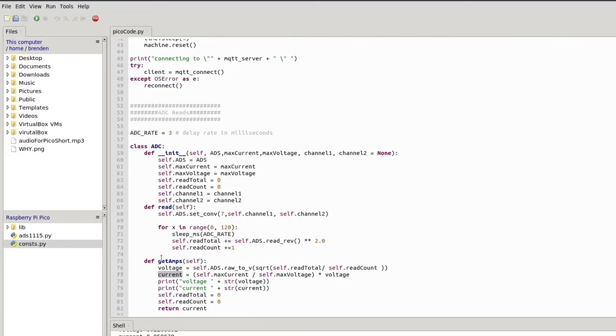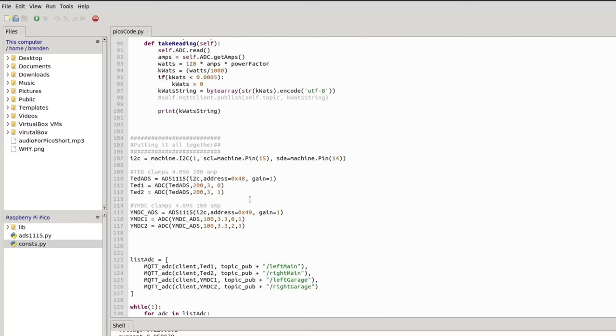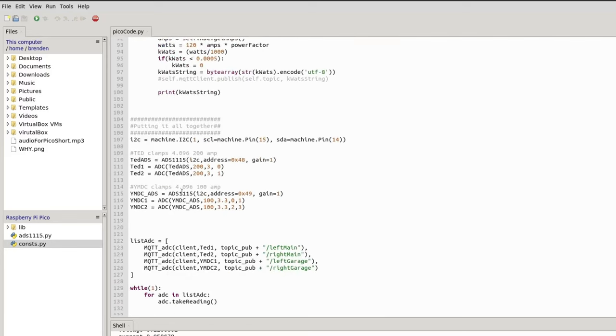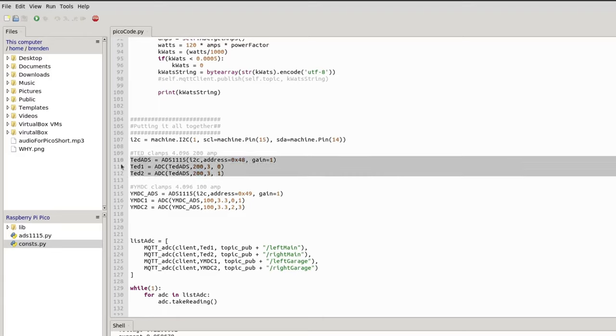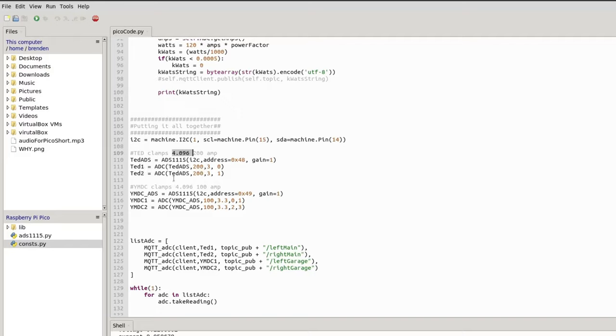These TED clamps have a gain of 1 which sets the range between negative 4.096 to positive 4.096. So that gives our theoretical max for the ADC. Now this clamp I have will never reach 4.096, it will only ever reach 3. And at 3 it's 200 amps.